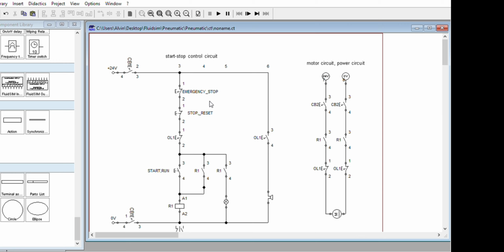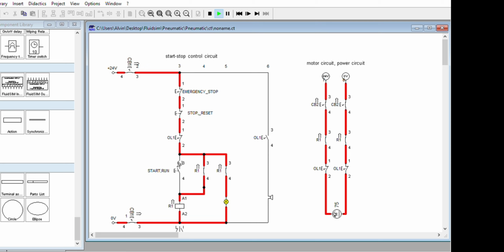There again. Turn on, turn on. Okay, you have the normal start stop. Okay, then turn on again, emergency stop, just in case. This is applied in, let's say, a conveyor. You are going to adjust something with the load. We are going for emergency stop and release again. Okay, and simulate the overload relay.